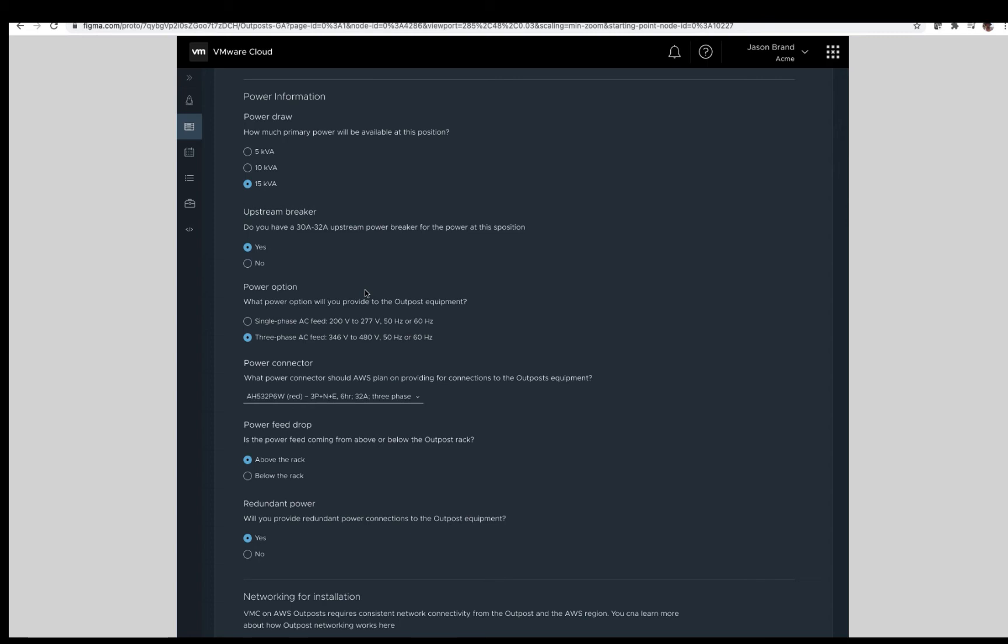Power connector. To connect the VMware Cloud on AWS Outposts to your power source, what power connections will best suffice for you? When ordering, there are options in the drop down. For today's order, we will be choosing red 32 amp three-phase connectors as shown here. Power feed drop. At the position, will the power come from above or below the rack? We will be selecting above the rack. Last for power, redundancy at the position. Will there be redundant power connections? We are selecting yes for today's order. For more information on power requirements for VMware Cloud on AWS Outposts can be found online at both AWS and VMware. If there are questions, please consult your VMware or AWS representative.